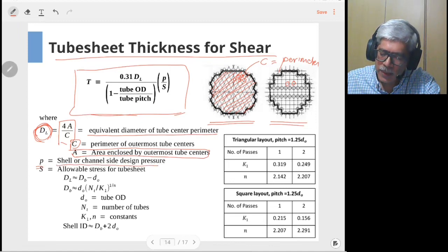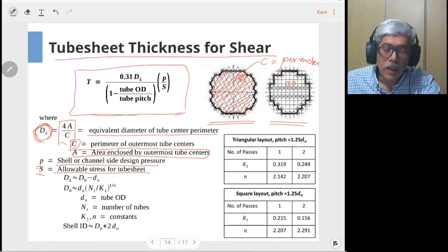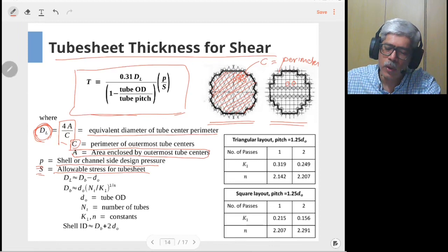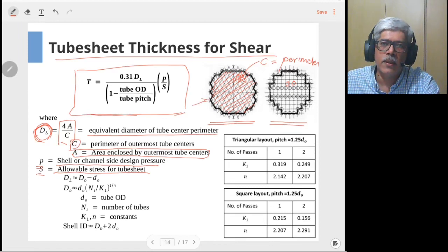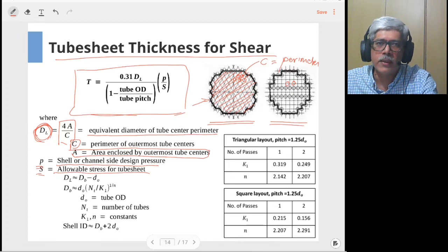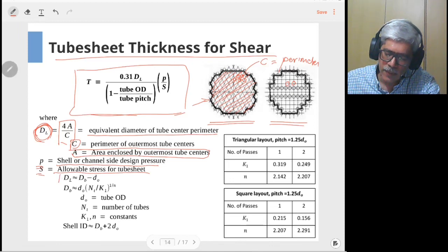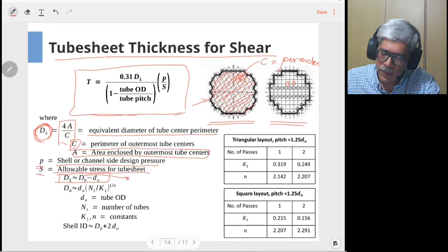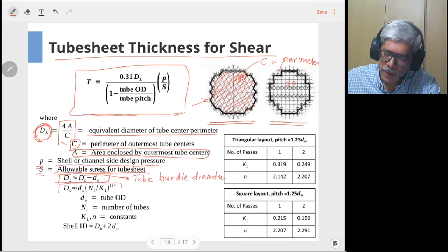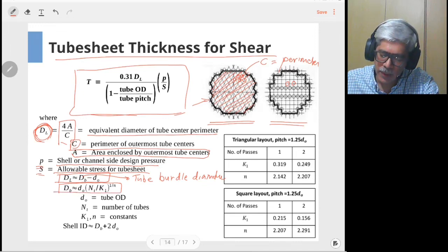P, as in the bending case, is either shell side or tube side pressure, whichever is higher, and S is the allowable stress of the tube sheet. In most cases, and specifically for the problems discussed here, you won't have the tube layout ready. Rather than drawing it in AutoCAD, the equivalent diameter DL can be approximated as Db minus Do, where Db is the tube bundle diameter.